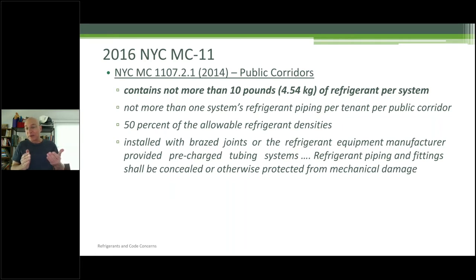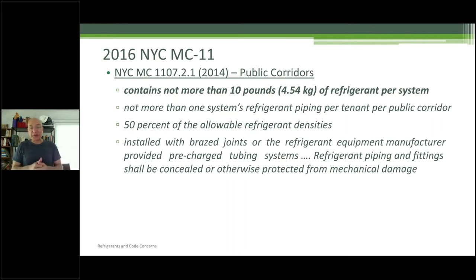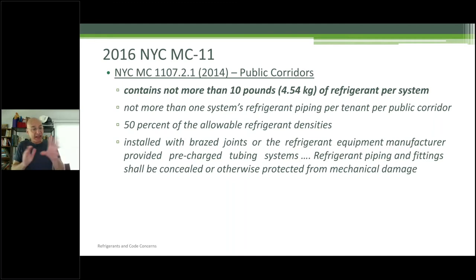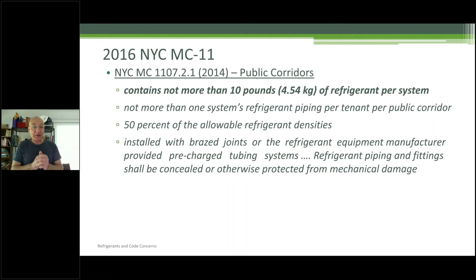What's the problem with that? The refrigerant is not flammable, so putting it in a fire-rated partition accomplishes nothing. And it's not gas-proof — if there's a leak, it may be fireproof but you still have holes for lights and cracks. The refrigerant is going to fall down into the corridor. We scratched our heads and said we've got to find a more scientific way of dealing with this, so the 10-pound rule is going away. Under the old code, you also couldn't have more than one system of refrigerant piping per tenant, and 50% of allowable refrigerant densities, installed with brazed joints.